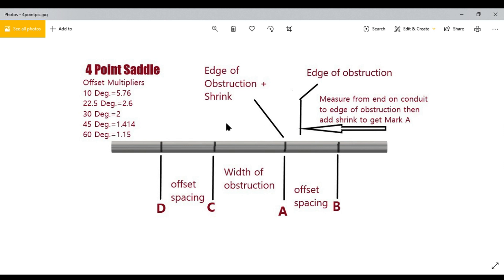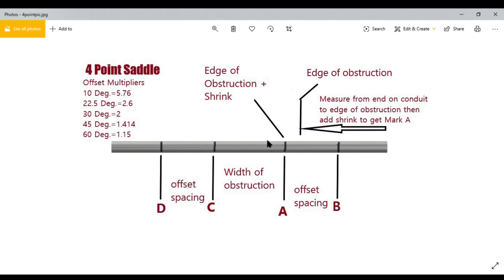After you've determined what degree of bend and what the shrink is, you can start laying it out. First, measure from the end of the pipe to the edge of the obstruction — not the center, the edge. Then add the shrink to that measurement. That gives you your first mark, which I'm calling Mark A. If you don't know how to get the shrink, you can go back to one of my other videos.